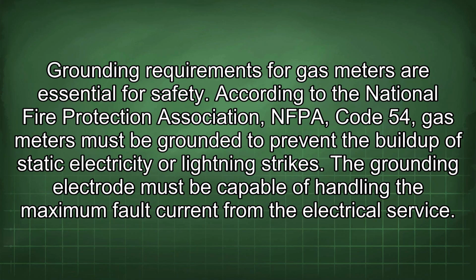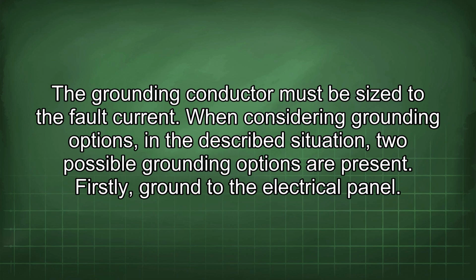Grounding requirements for gas meters are essential for safety. According to the National Fire Protection Association (NFPA) Code 54, gas meters must be grounded to prevent the buildup of static electricity or lightning strikes. The grounding electrode must be capable of handling the maximum fault current from the electrical service. The grounding conductor must be sized to the fault current.